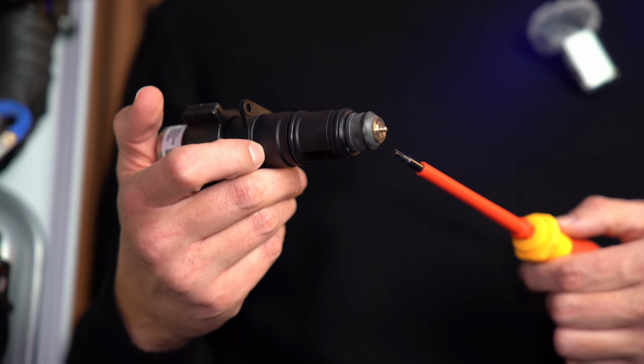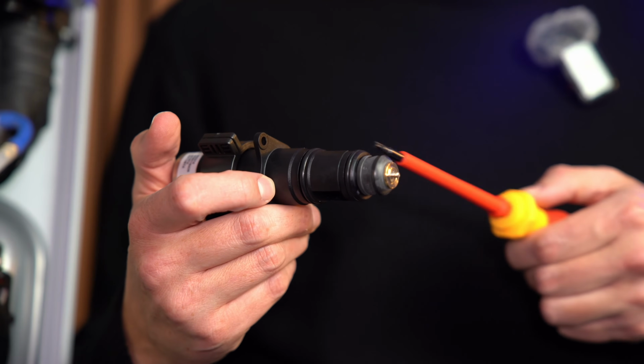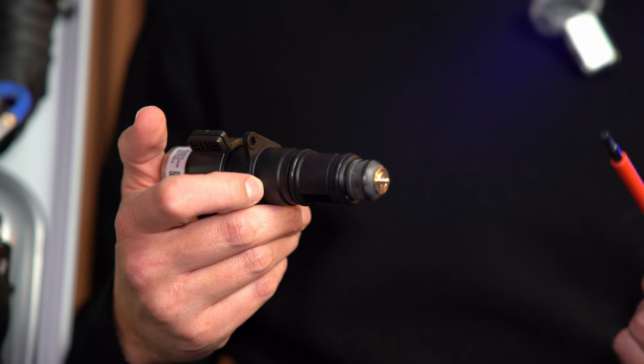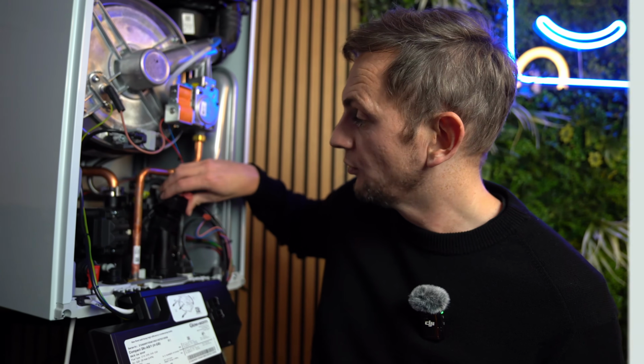This cartridge can't be rebuilt and repaired, it just needs to be replaced, but they're really inexpensive. These are common failure parts on all combi boilers, but the peace of mind here is if it does fail, it's pretty easy to access and shouldn't take an engineer too long to swap out.